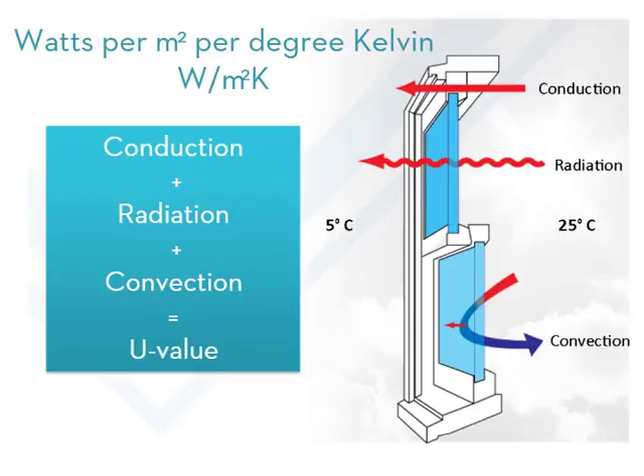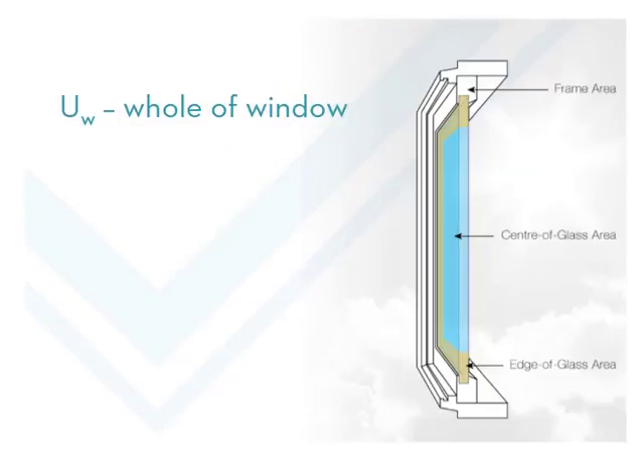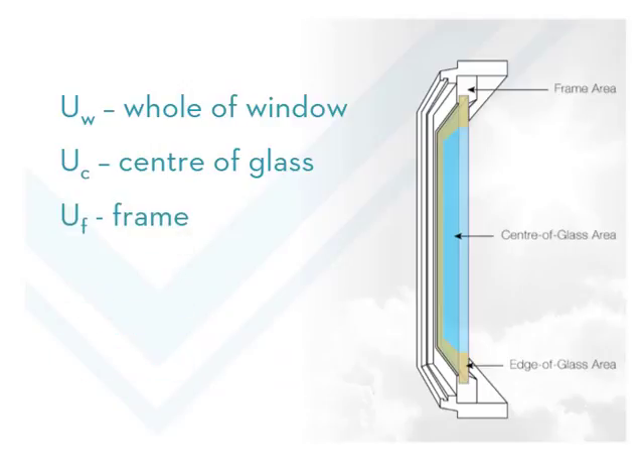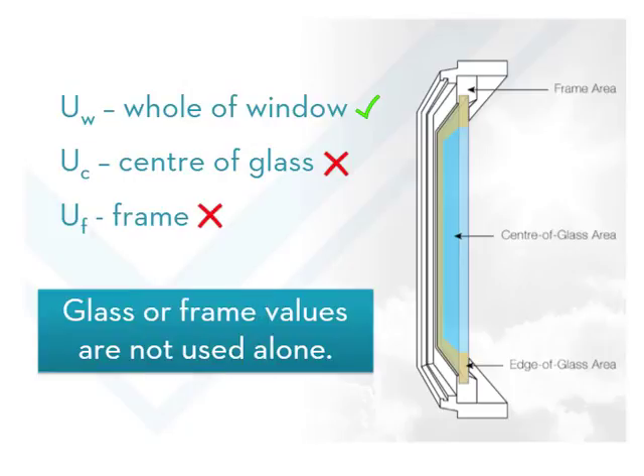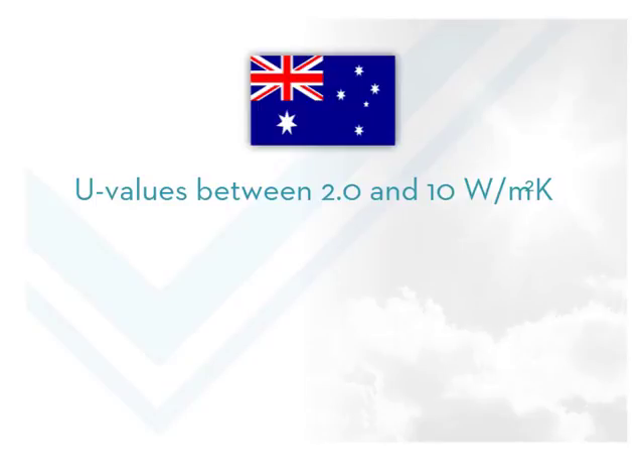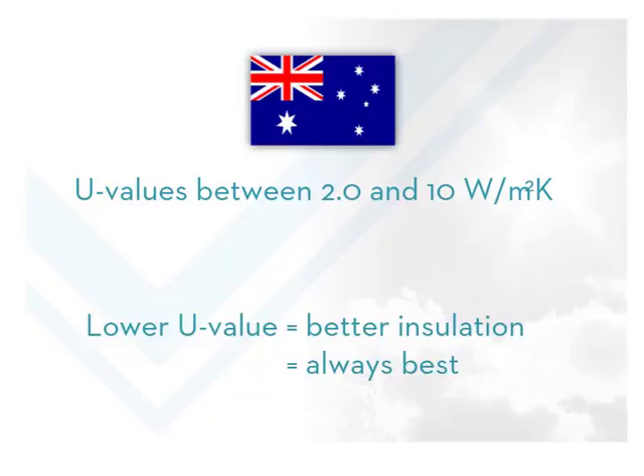U-value is expressed in terms of watts per meter squared per degree Kelvin. The U-value for a window takes into account the various U-values for components making up the window. You can see these abbreviations in technical literature: Uw is the value for the whole window and the only acceptable measurement for use in energy rating programs, often simply abbreviated to U. Uc is the value at the centre of glass, and Uf is the value for the frame. U-value ratings generally fall between 2 and 10 watts per meter squared Kelvin for Australian products. A lower U-value indicates a window's greater resistance to heat flow and therefore a better insulating performance.